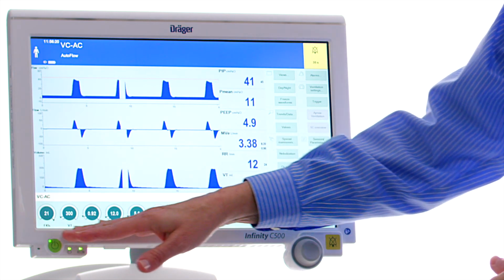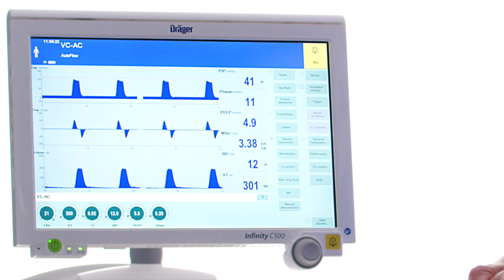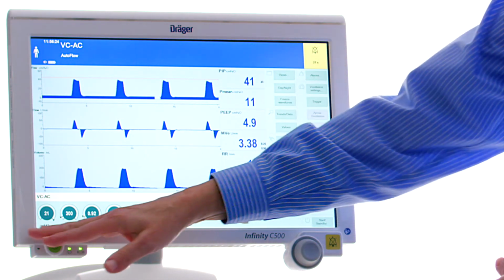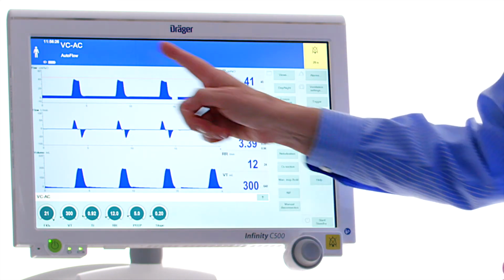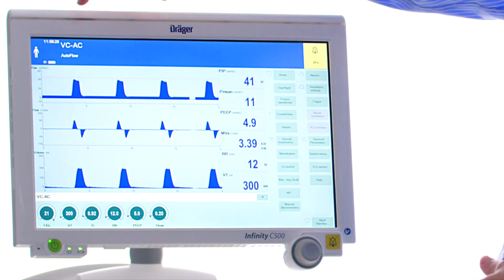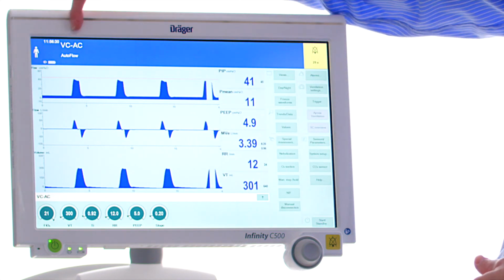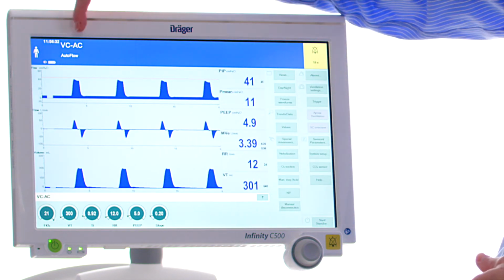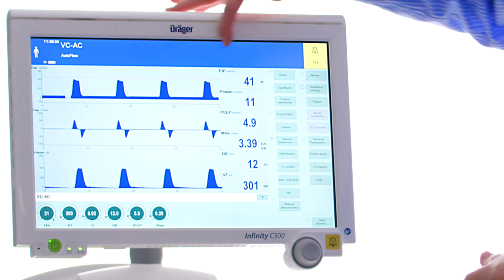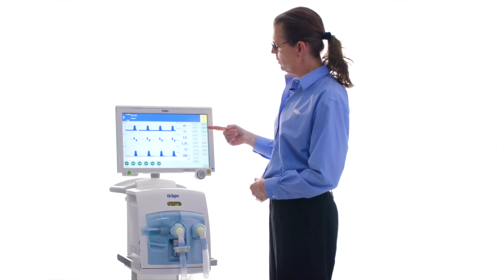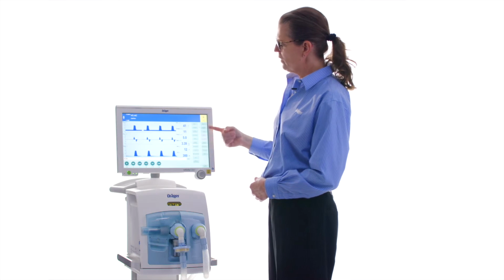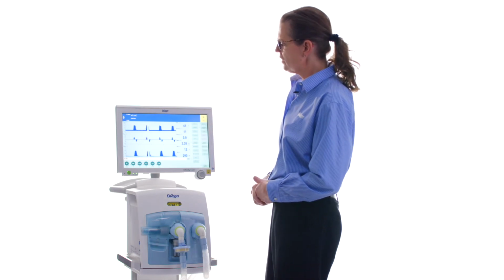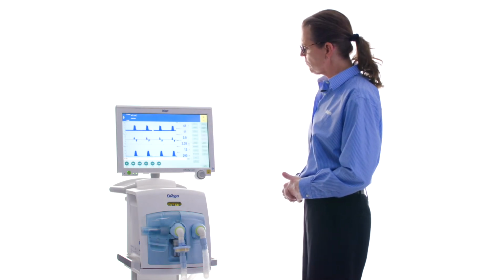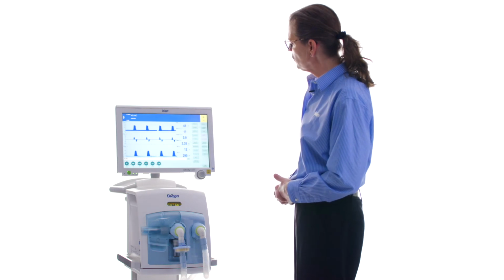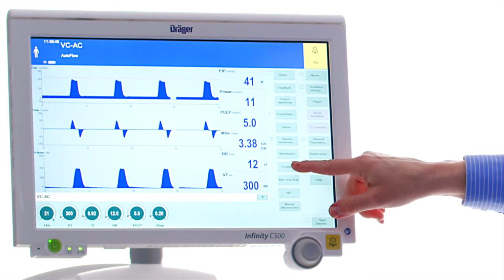So we have our ventilation settings that sit across the bottom. Anything blue is measured, green is set. The graphics are in the center. Your mode of ventilation will be displayed at the top of the header bar with any active adjuncts and then alarms across the top. We then have configure buttons, which are shortcuts to the functions that you will use most often. One of the most commonly used configure buttons is your O2 suction.